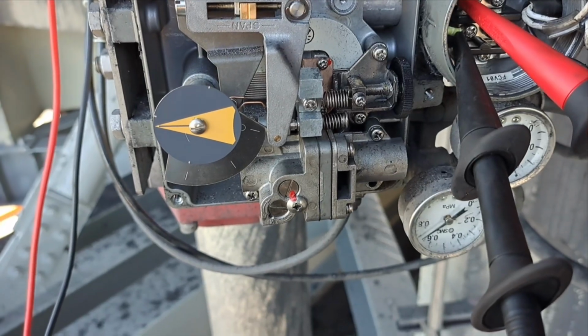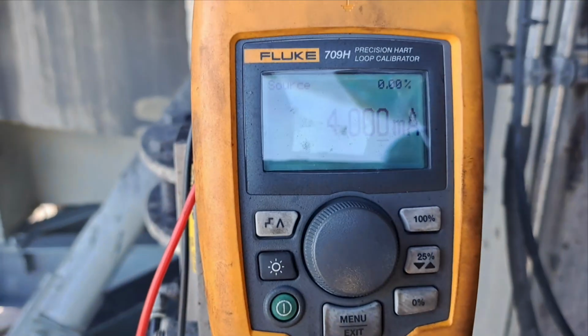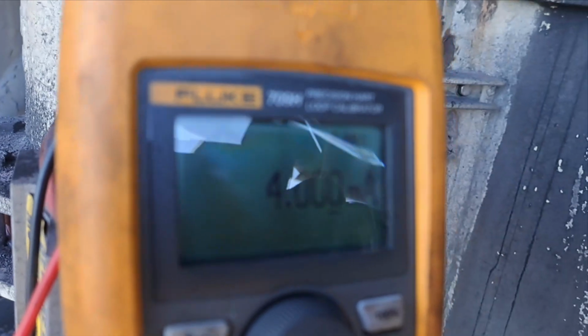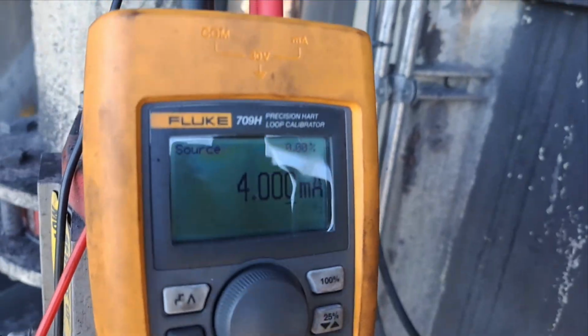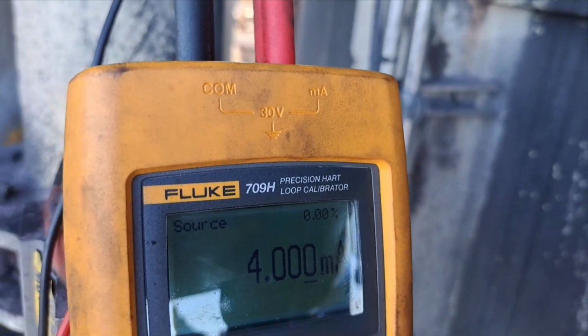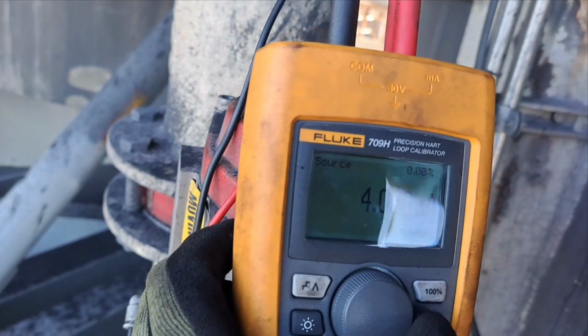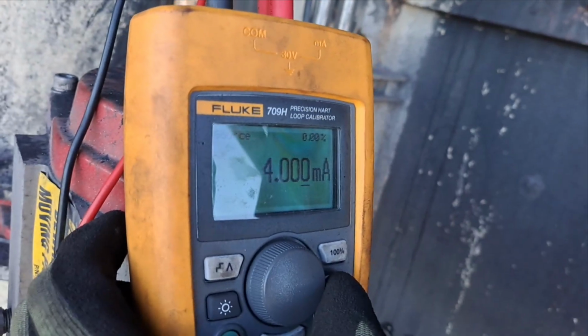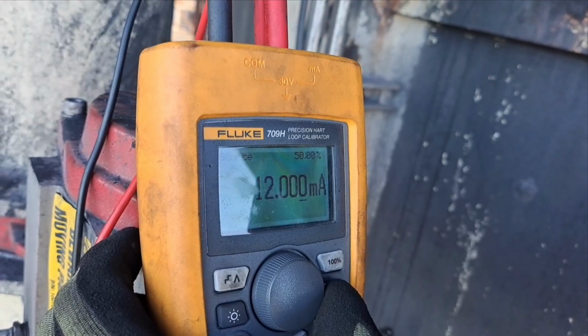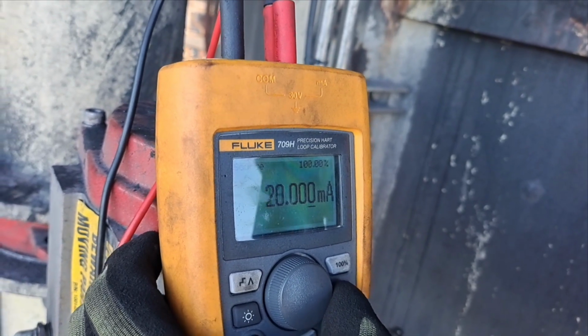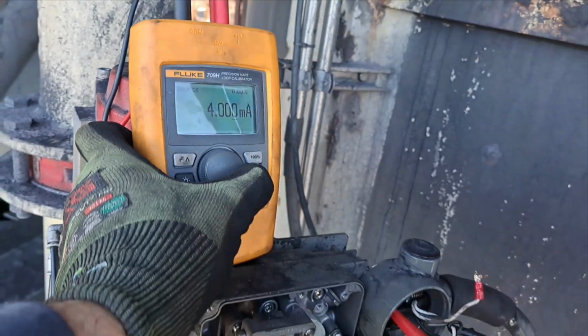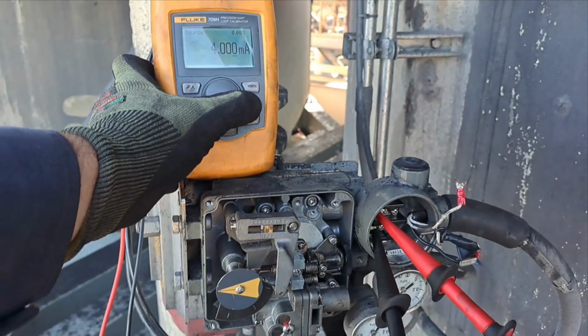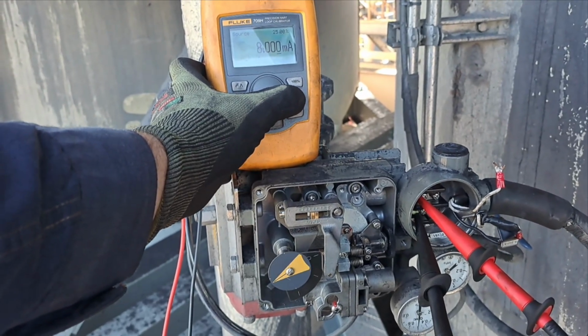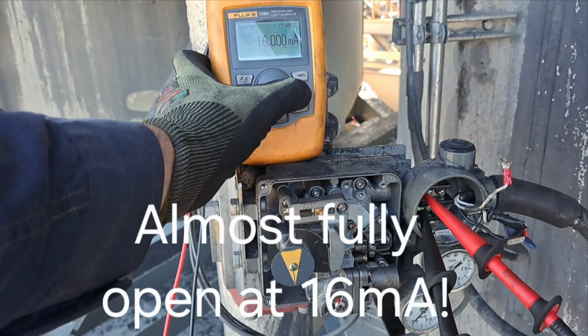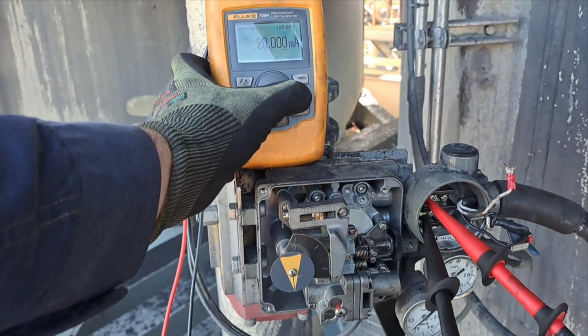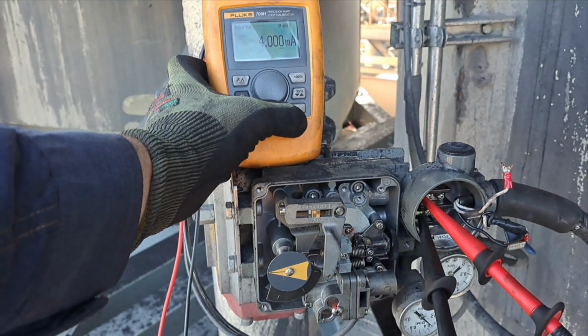With the pilot valve successfully replaced, I move on to calibration checks. I disconnect the signal cable and hooked up a loop calibrator, giving me direct control of the positioner signal. Then I perform an as-found calibration check to identify any parameters that need adjusting. It is clear that the span is off by a significant margin, but before adjusting the span, I start with the zero calibration.